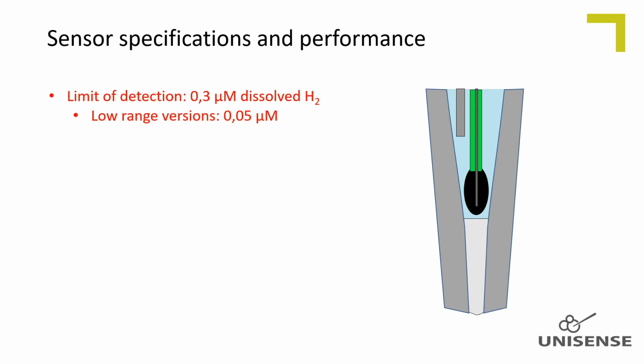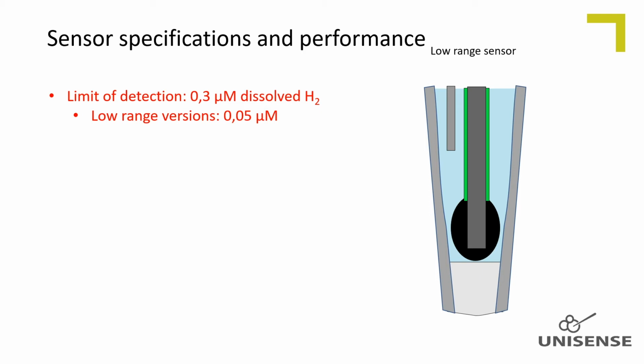I will now turn to the actual performance and specs of the hydrogen sensors and give some comments to them. Recall that these specs are only guaranteed with use of a Unisense meter. The limit of detection is stated to be 0.3 micromolar dissolved hydrogen. However, the detection limit is strongly influenced by the application in question. By producing the hydrogen sensors with a wider tip membrane, the sensors can be made more sensitive with a detection limit down to 50 nanomolar. The lower detection limit will, however, increase the sensitivity to stirring.